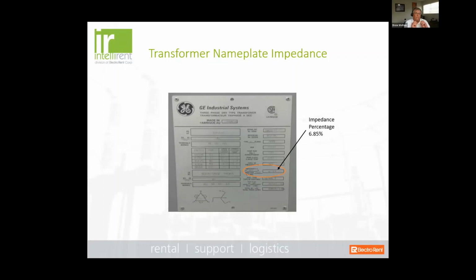So, one of the very, very important things, not only as a protective relay guy or field technician for relaying, but also for people doing diagnostic testing on a transformer, is to be as familiar as you possibly can with the nameplate rating of the transformer. I mean, this is basically how you set your protective relay elements based on this information. This is also how you compare diagnostic test results for certain tests. And one of those is leakage reactance, because before the transformer leaves the factory, they're going to measure that impedance in percent and stamp it right onto the nameplate. And that's what we see here in this illustration.